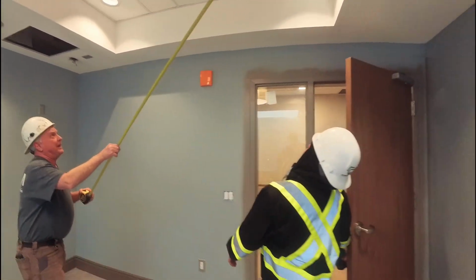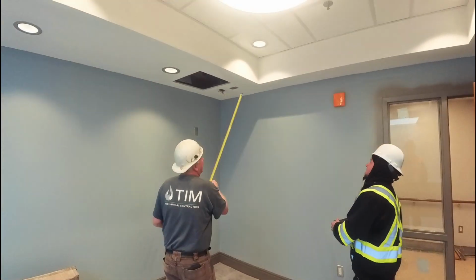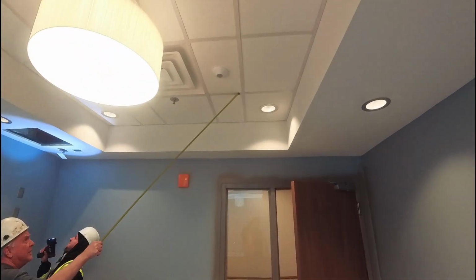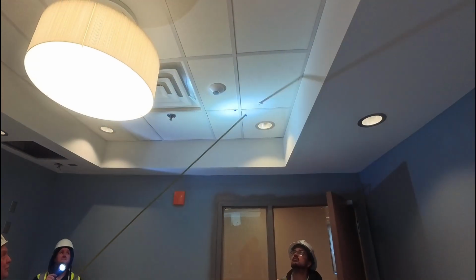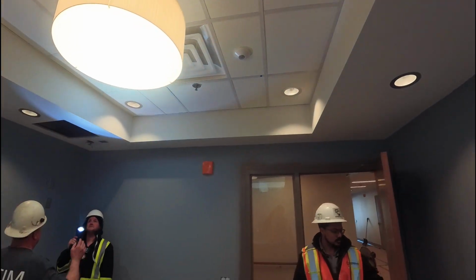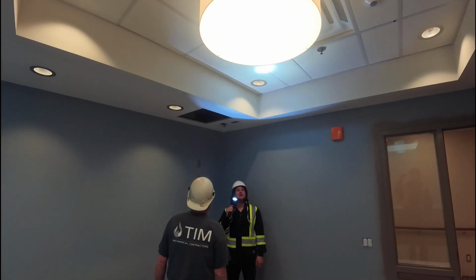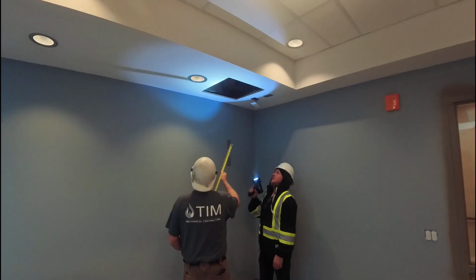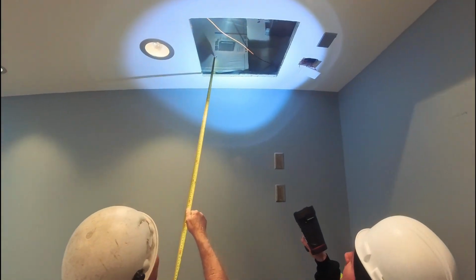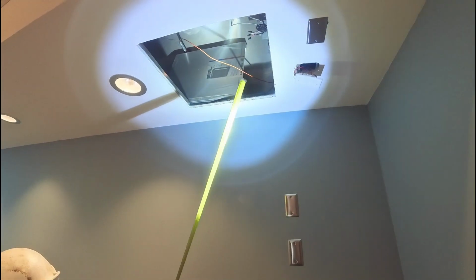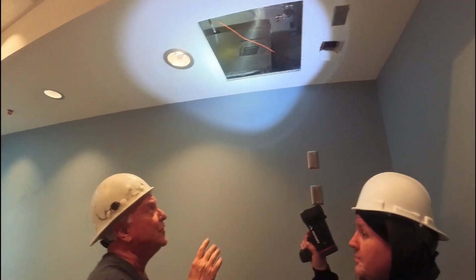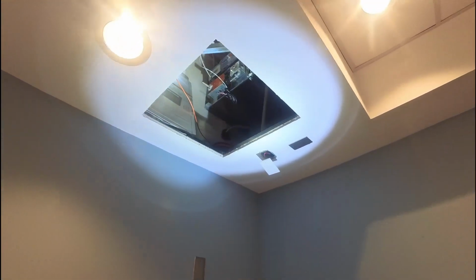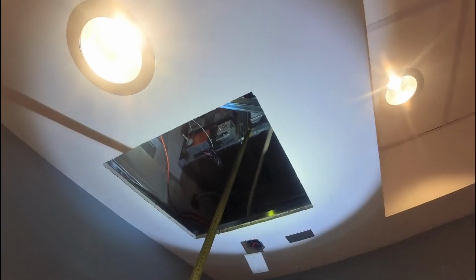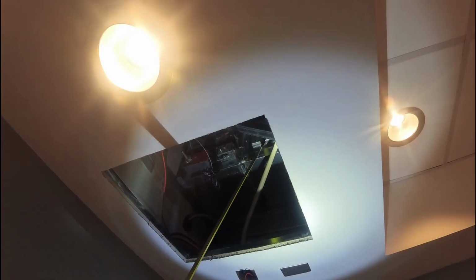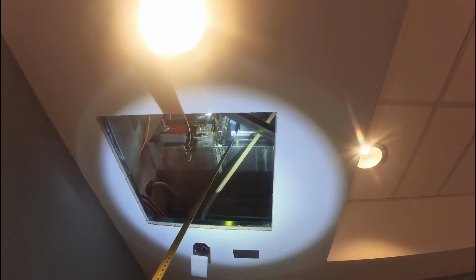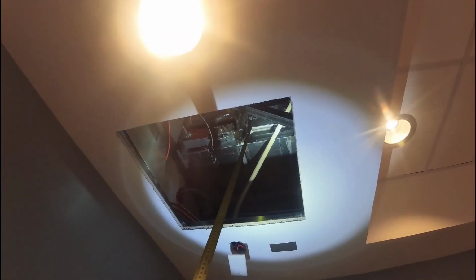Well, here's the second VAV, the one that picks up, it goes through the wall here. No, there'll be no filter. Filter in here? No, that's a fire damper. See the blue circle? Yes. The blue circle suggests that there's a VAV right there for the controls guy to do his service work. So there's an access door that I put in there the other day. Once it's installed, I will have one of those FSD stickers stuck to that door so that you know there's your fire smoke damper again to be looked at. Again, the access door is an observation portal to look inside the damper, etc., right?